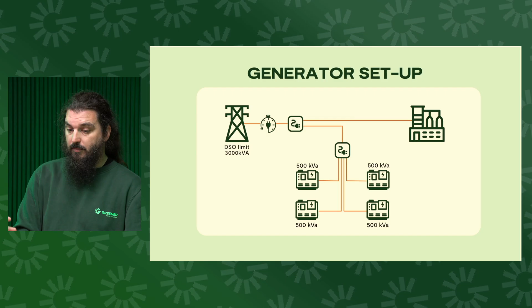Yeah. So you can imagine if these are running, you've only got blocks of energy that you can use. So when the demand goes over the 3 MVA mark, the generators will kick start in, but then they're going to run for a certain amount of time and at a certain power, which is not as flexible as could have been used. That also means any over generation. So if the site load does drop below the 3 MVA limit, then the generators are still online. Any additional energy being generated by those diesel engines is going to make its way straight back across to the grid, and you're just throwing that generation away.